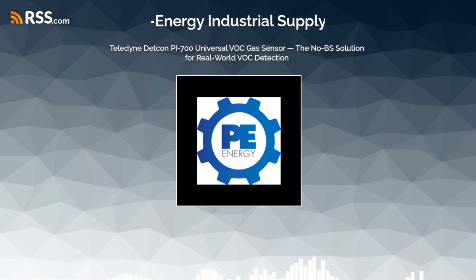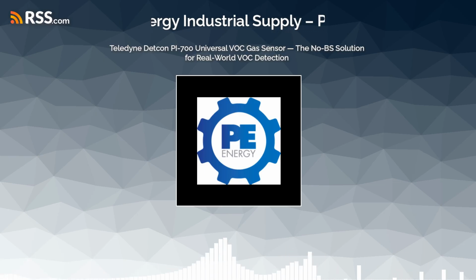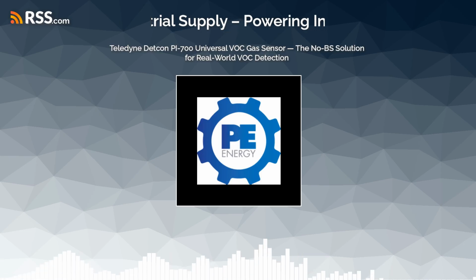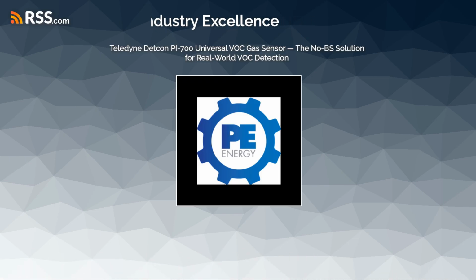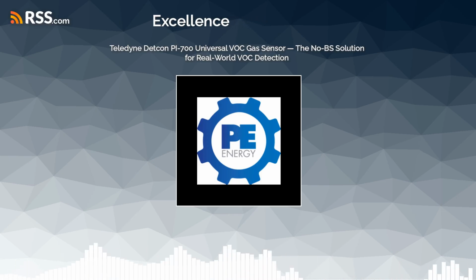Let's round out the hardware specs with power and integration, because this thing is surprisingly efficient. It runs on 11.5 to 28 volts DC and consumes less than 2 watts of power. That ultra-low power consumption is actually very significant for facility design, because of the scale. If you have a massive processing plant with 500 of these detectors deployed, the difference between a sensor drawing 2 watts versus 5 watts is a massive difference in your central power supply requirements, especially when you have to size your backup battery arrays to keep the safety systems running during a total power outage. That makes a lot of sense.